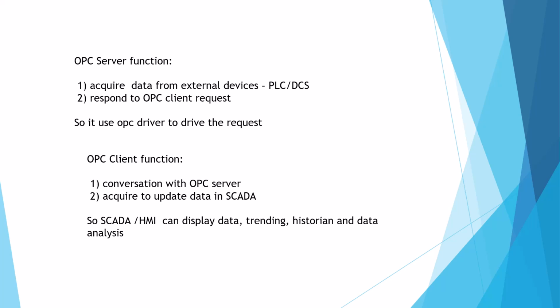The OPC server function is to acquire data from external devices, PLC or DCS. That means it picks up data from the PLC or DCS, and responds to the OPC client request, then sends data to the OPC client. To do this, you have to use an OPC driver to handle the request. The OPC client function is a conversation with the OPC server, acquiring and updating data in SCADA. So the SCADA HMI can display the data, trending, history, and data analysis.